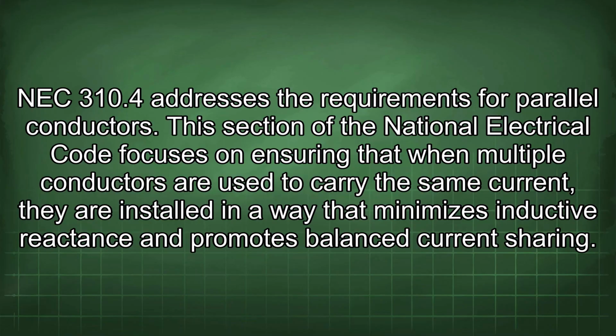NEC 310.4 addresses the requirements for parallel conductors. This section of the National Electrical Code focuses on ensuring that when multiple conductors are used to carry the same current, they are installed in a way that minimizes inductive reactance and promotes balanced current sharing.